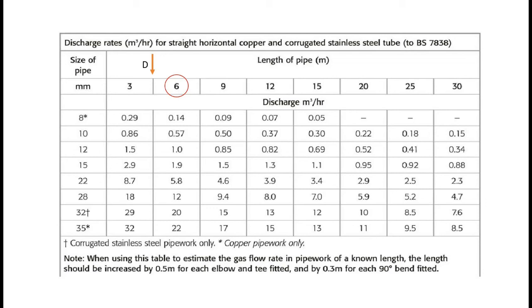Once we've worked the top row out, we look down the column until we come to a number that's either equivalent or the first number that's larger than our discharge rate that we require. In this case, the A box on our grid was one, and the number in the A box is the number you're looking for down that column.